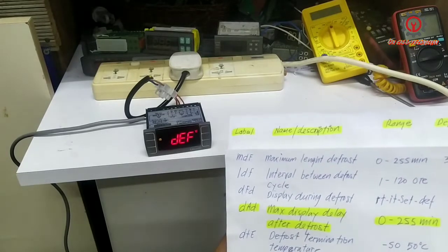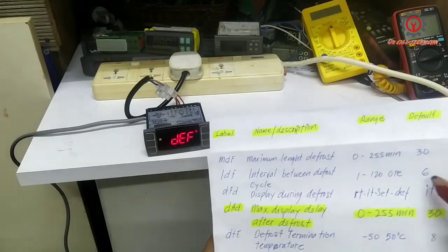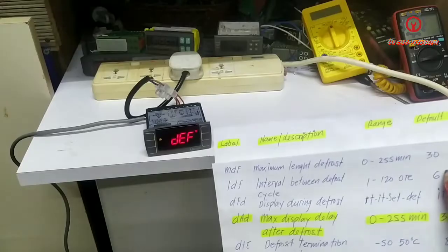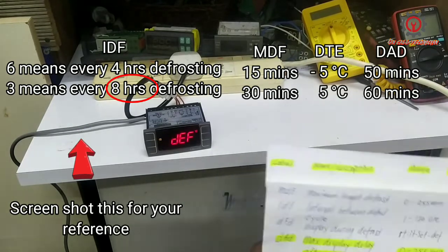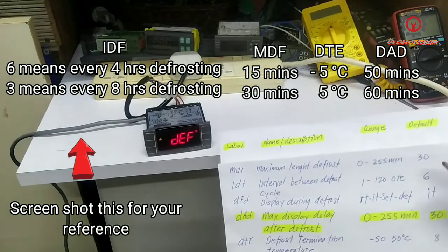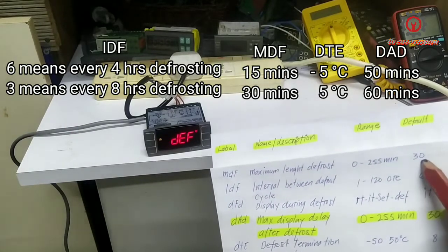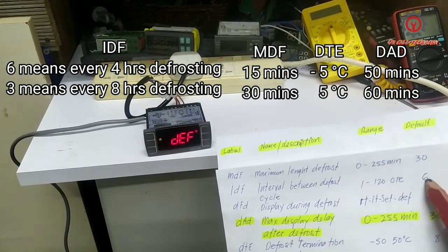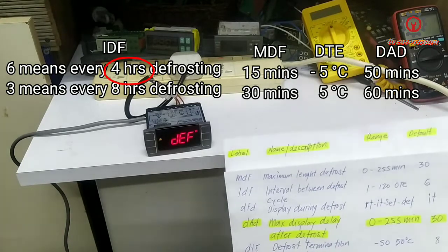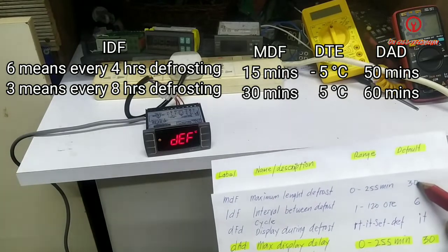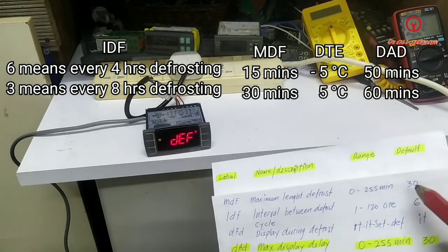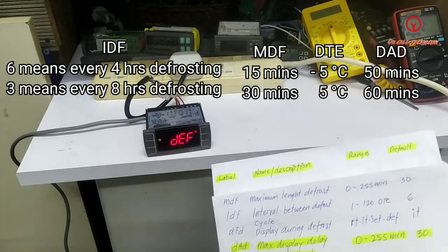You may also lessen the interval between defrost cycles. If the restaurant or supermarket you're working in is busy, meaning the door is frequently open, change this 6 to 3 so that every 8 hours this control will defrost. The maximum length of defrost for MDF ideal is 30 minutes. But if you're going to set it for 6 hours, meaning every 4 hours your unit will defrost, you need to lower this 30 minutes to 20 or 15, it depends.